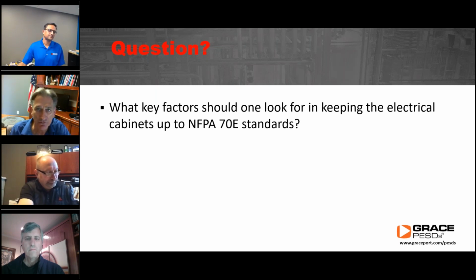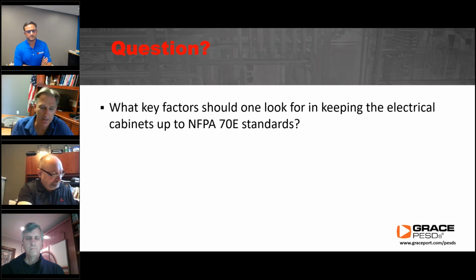The first three are the most effective. The last three are the least effective. This particular question, I would think, really can be affected by number 3, engineering controls that can be built into control panels for safety. Even things like touch safe or finger safe are mentioned in one of the informative annexes in the back. Even substitution would be an example, maybe changing the control wiring in a motor control center from 120 volts down to 24 or 48 volts to make it a bit safer. But it comes back to what Terry had already mentioned, which will probably be mentioned a lot today: risk assessment.